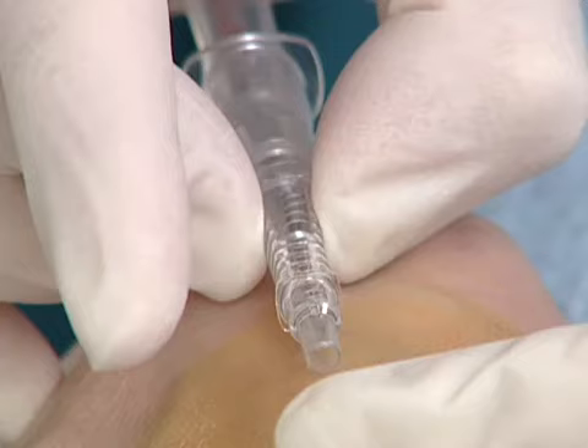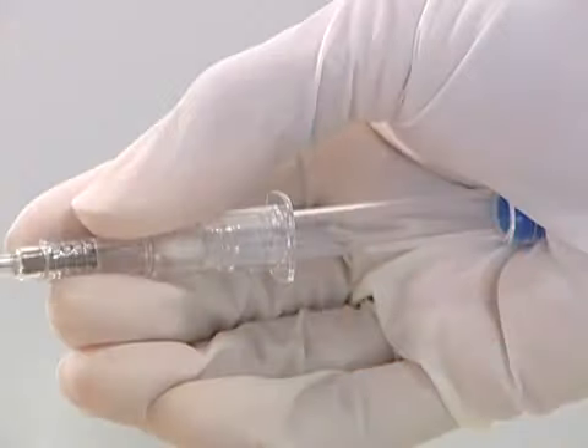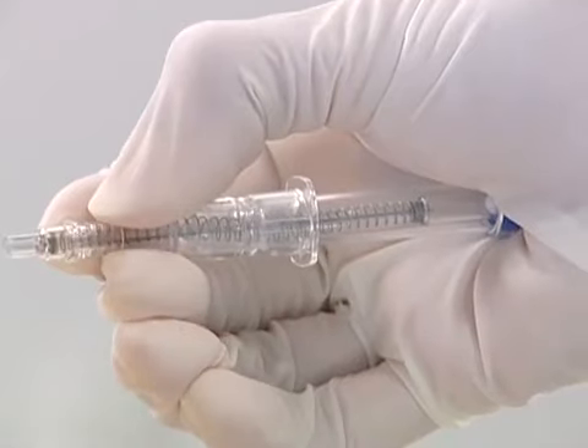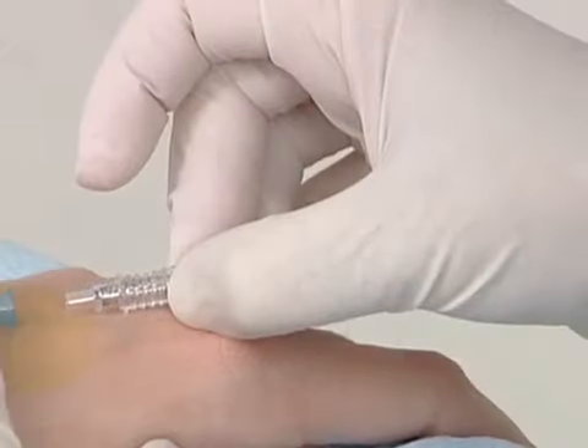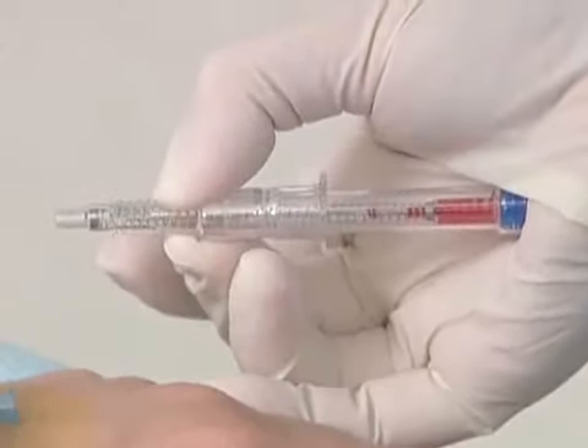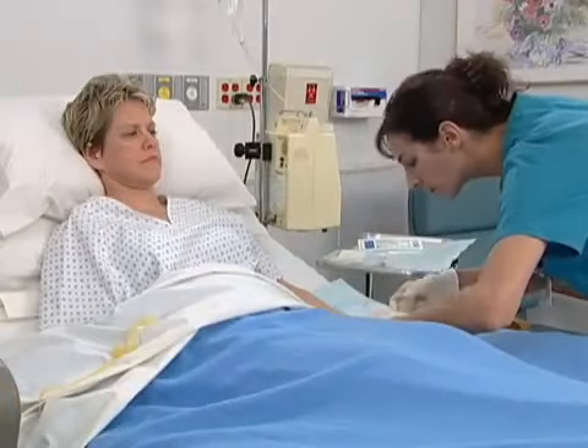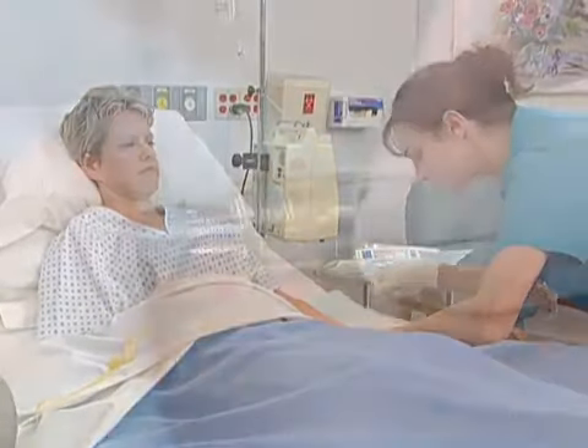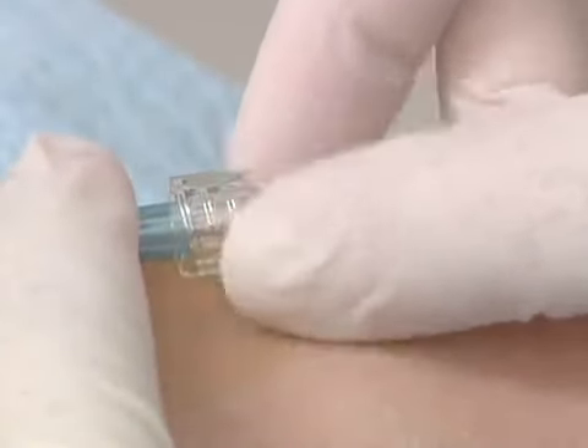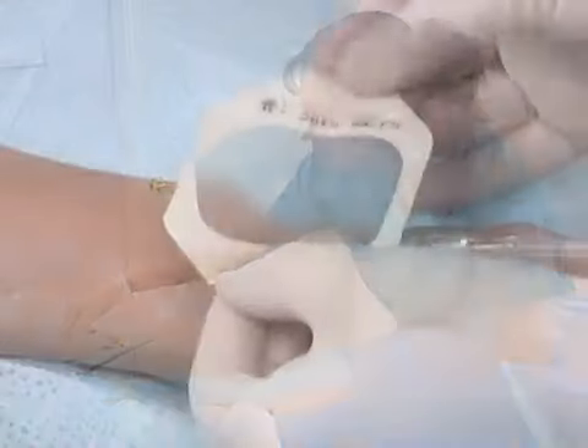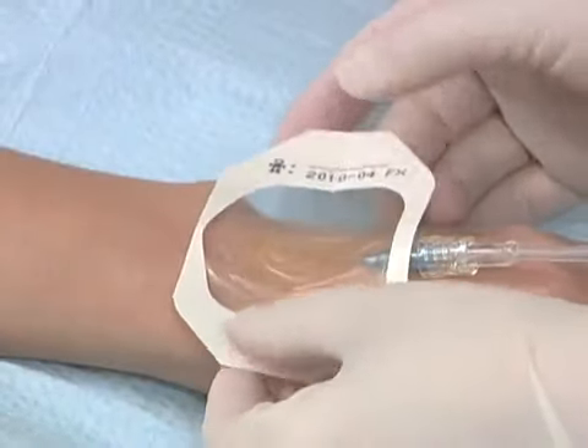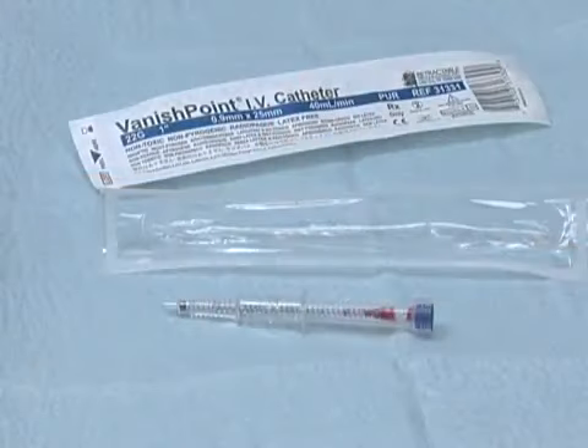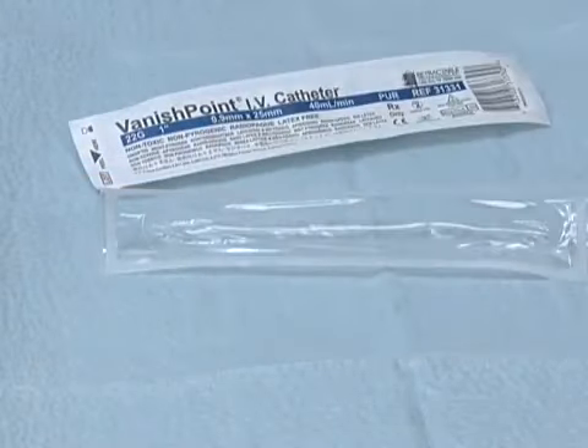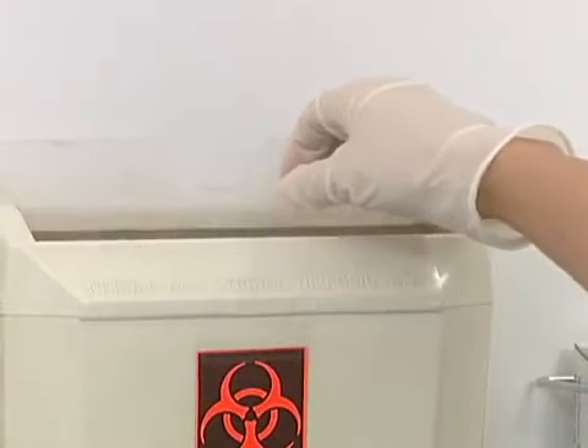Let's see that action again from below. Note that the end of the housing is pressed into the palm. Pull back on the finger grips and the needle retracts into the housing, reducing the risk of a needle stick injury. You can see the spring and needle entirely within the clear housing. Then attach IV tubing or an adapter to the catheter hub as you normally would. Secure the catheter in place and dress the site in accordance with your facility's protocol. Dispose of the introducer needle in an appropriate Sharps container, following the policy of your institution.